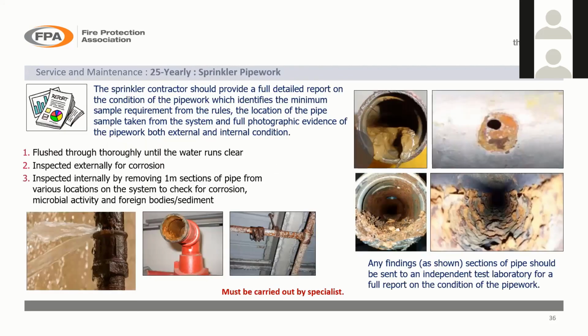So we're almost at the end now. We've got 25-year testing. The idea here is that you should flush your system through until the water runs clear, and then you should check internally and externally the condition of the pipework and the sprinkler heads. The sprinkler pipework, what you need to do is actually take some sections out, have a look in the pipe. If it shows any signs of any pitting or anything else, or corrosion, or is rusting away, take some pictures.